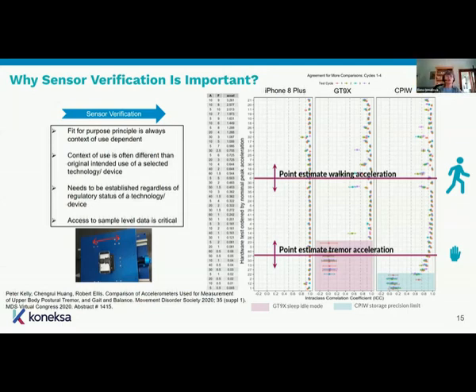So as you know, the first step is sensor verification. To understand the accuracy of accelerometers embedded in all these 3 devices I described in the previous slide deck, we put them on top of the shake table, which is the gold standard benchtop device for evaluating sensor accuracy. What this table does is move with different amplitudes and frequencies that you see in the gray cells in the middle of the slide, which result in different accelerations.